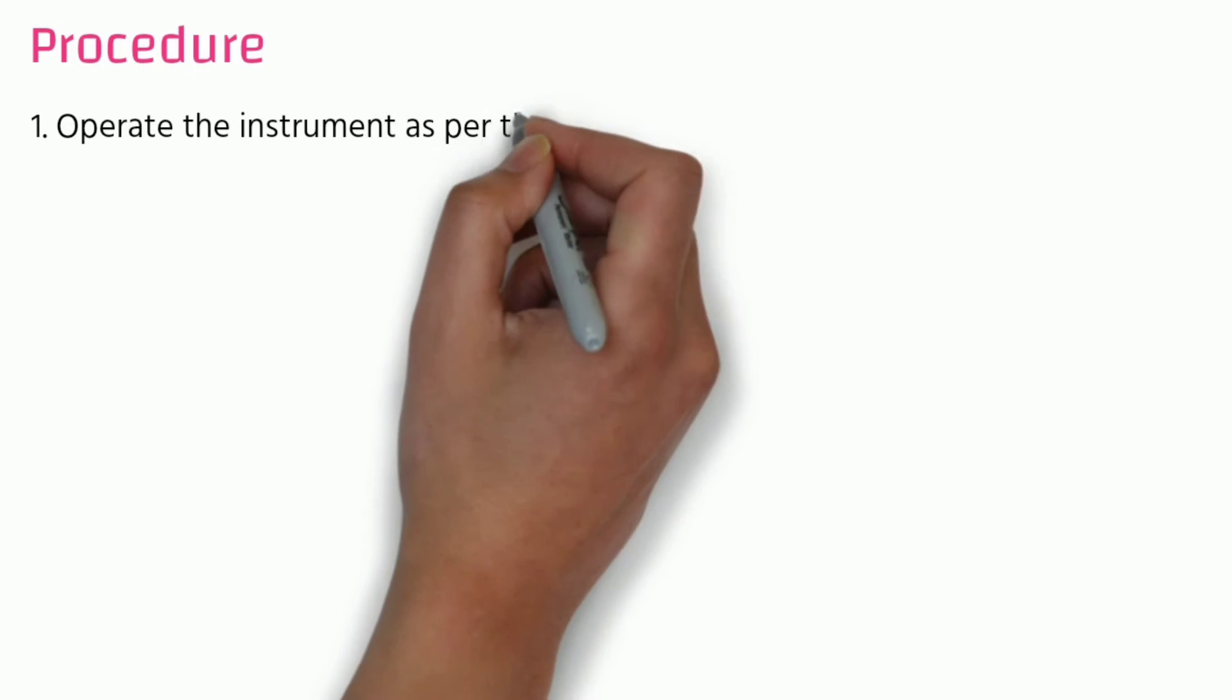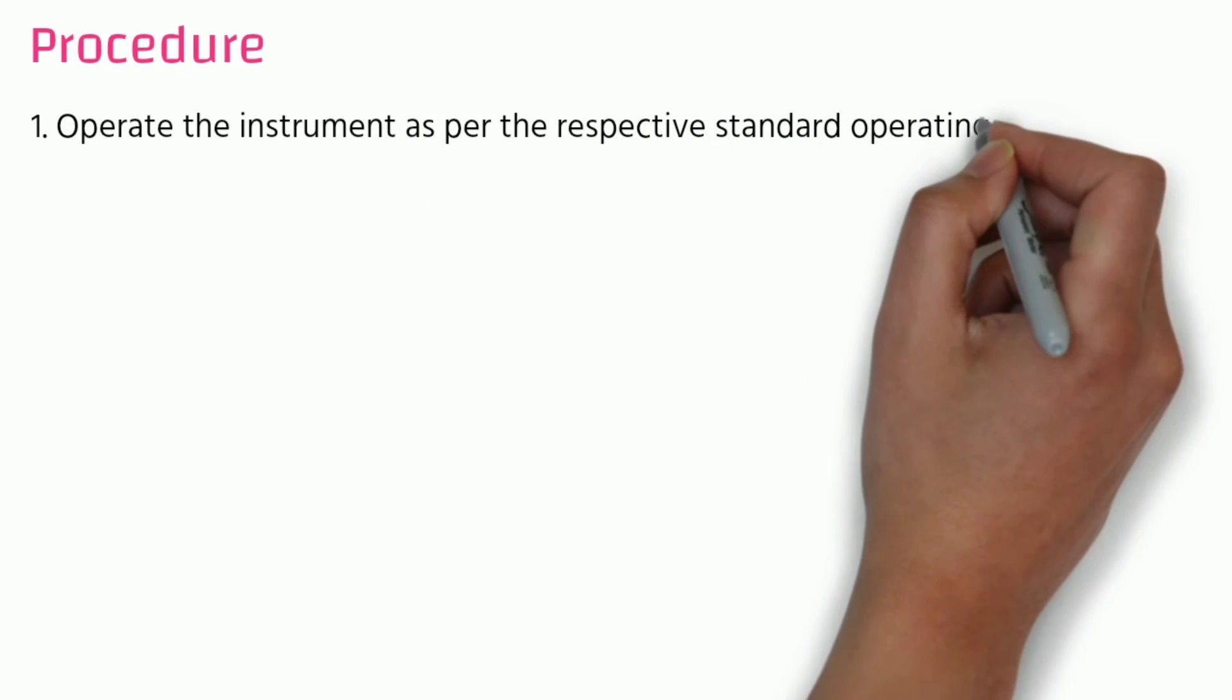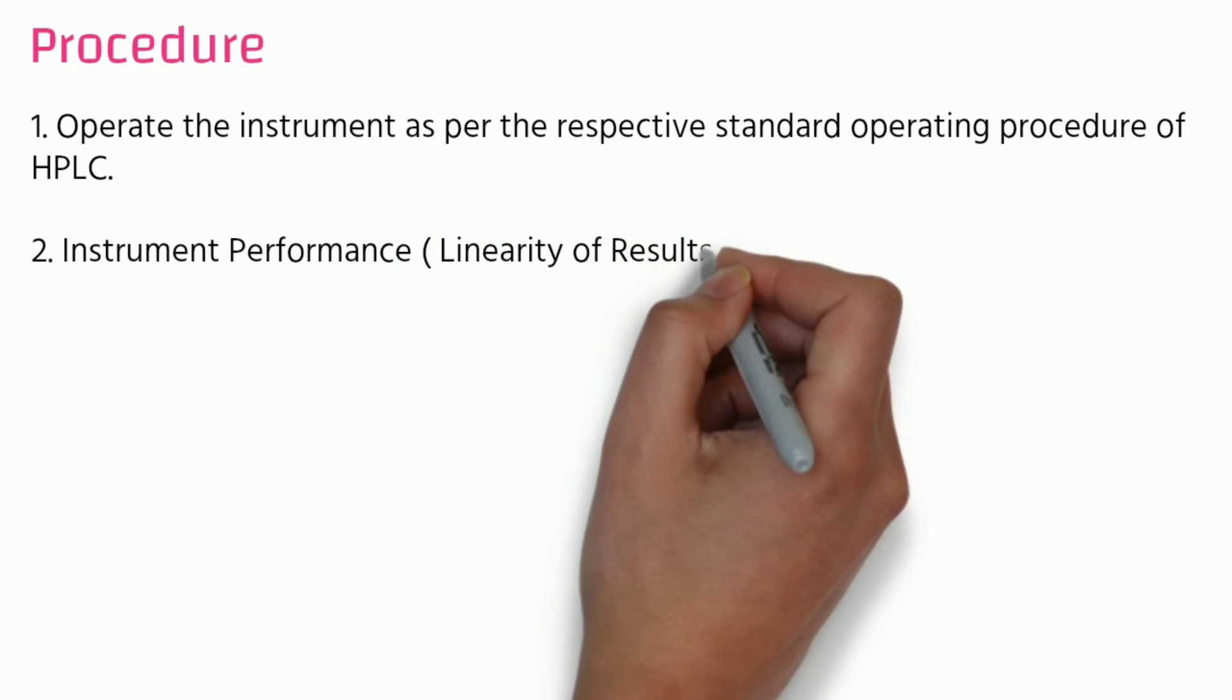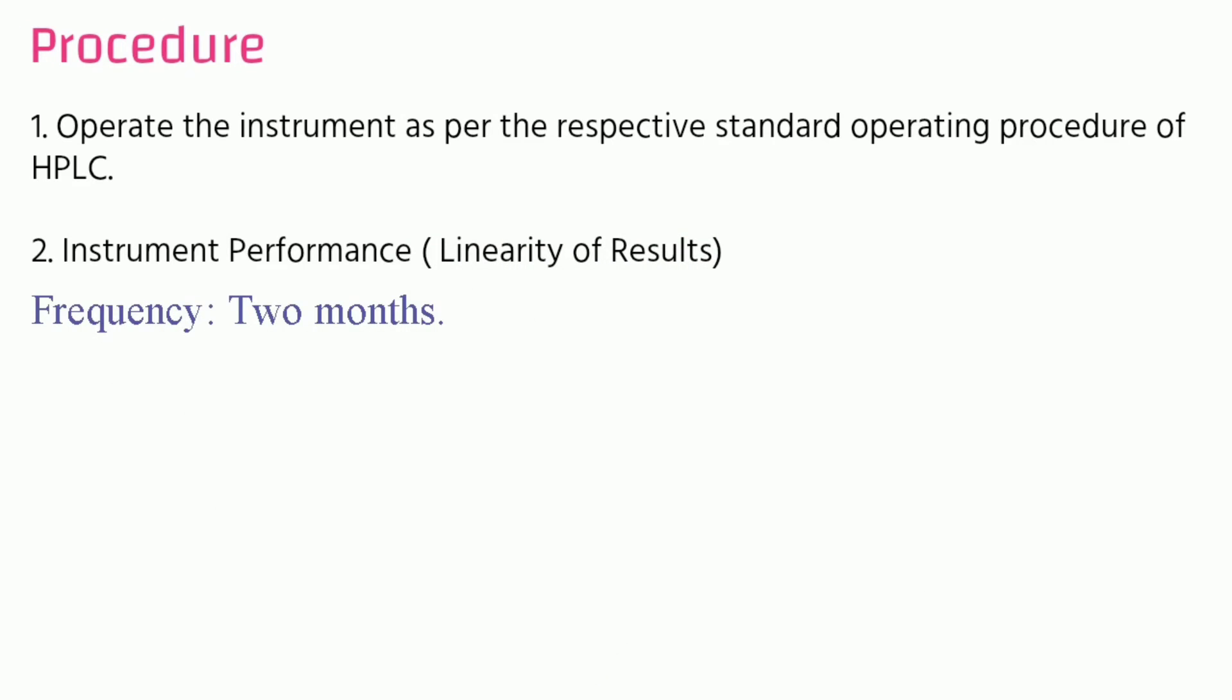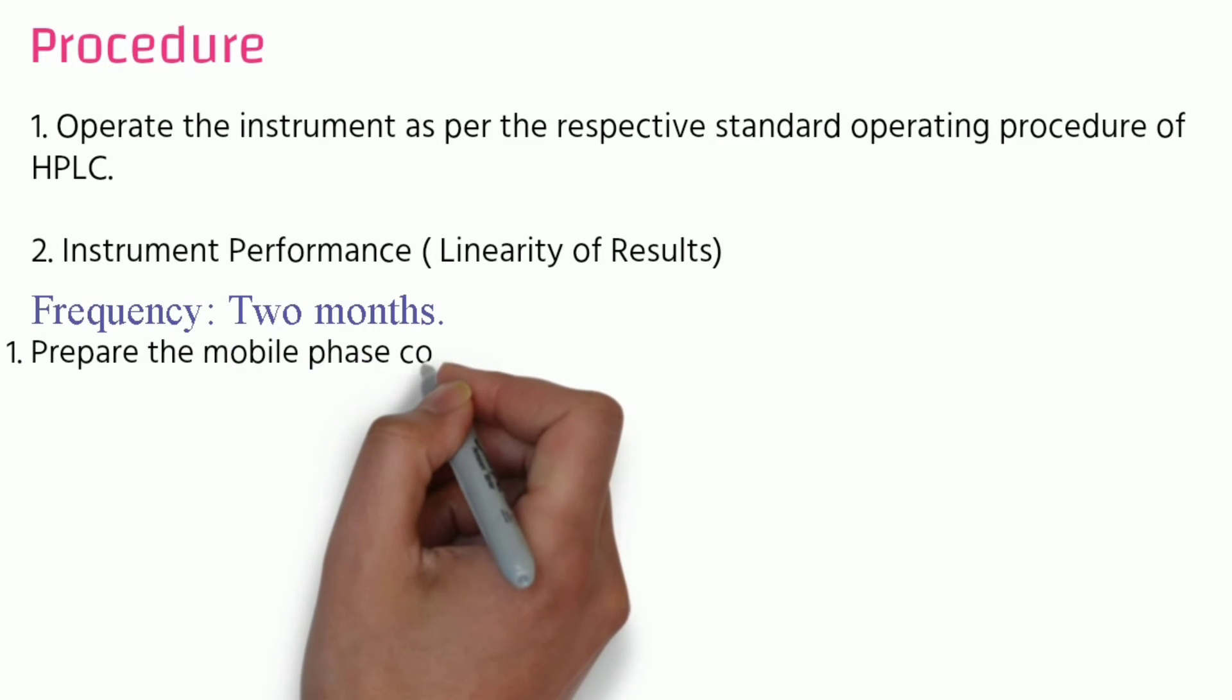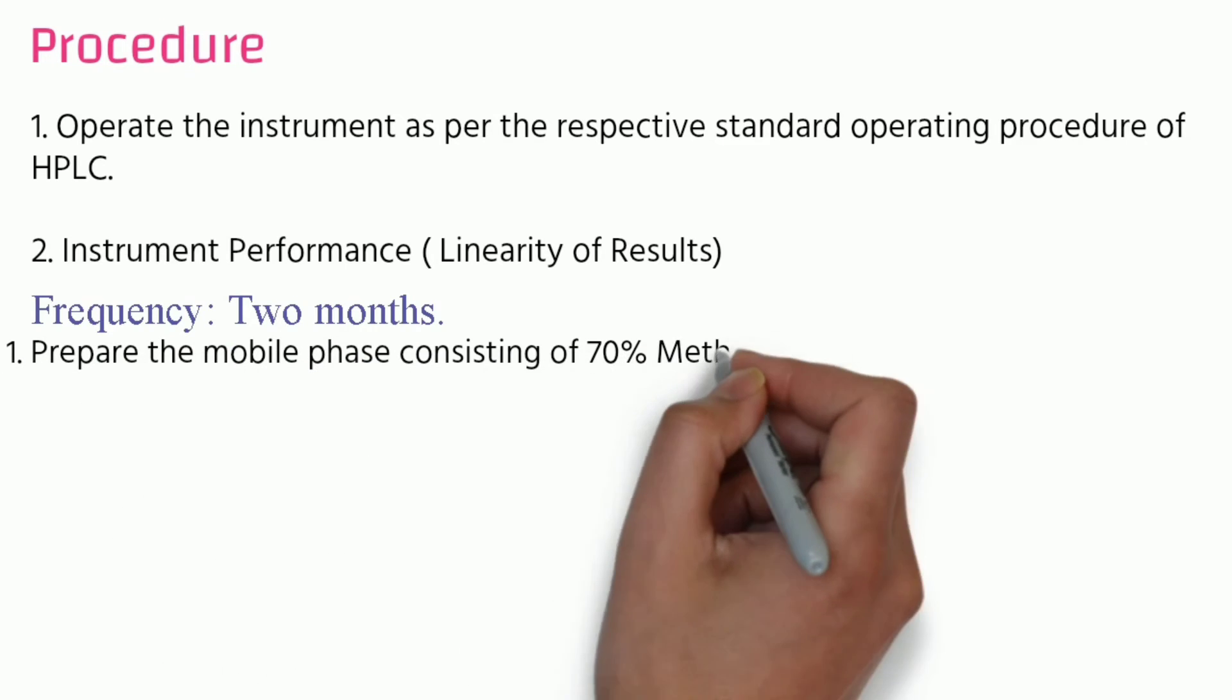Its procedure: Operate the instrument as per respective standard operating procedure of the HPLC. Instrument performance of linearity of results. Frequency: two months. Prepare the mobile phase consisting of 70 percent methanol and 30 percent water.